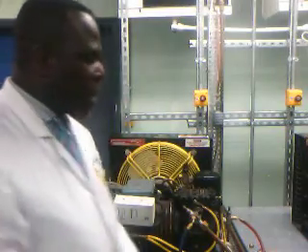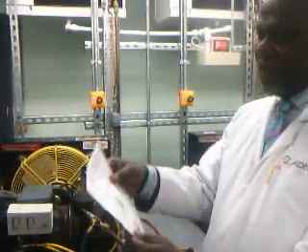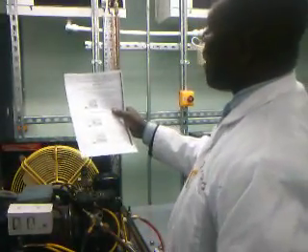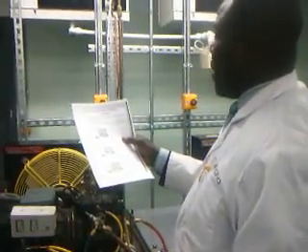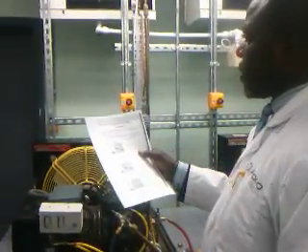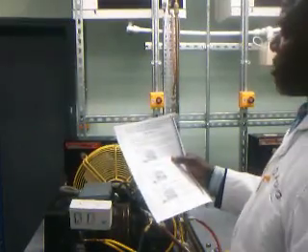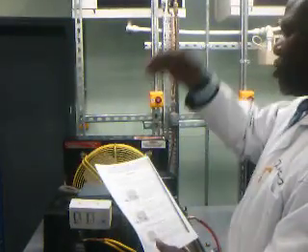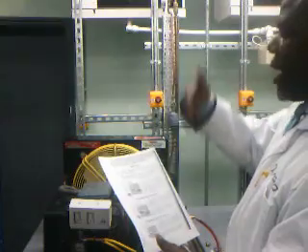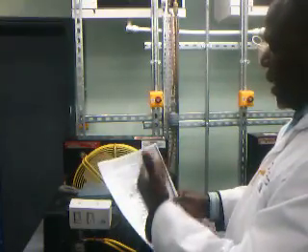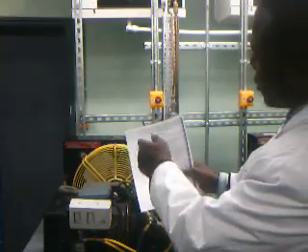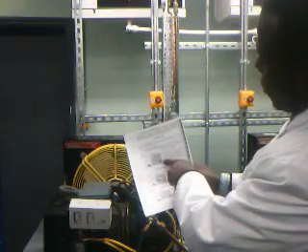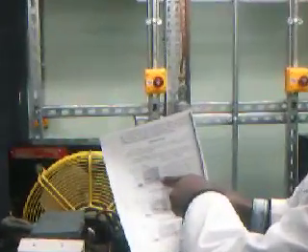That is why, if you look at the handout I've given you, you can see the first example. The first example says roughly refrigerant enters the condenser at a temperature of, say, 70 degrees C. It will desuperheat at the top, and then it continues to change state, and by the time it gets to a point close to the bottom pipe, you have the temperature coming down to 39. So the condensation at 39 continues throughout the surface of the condenser towards the end.